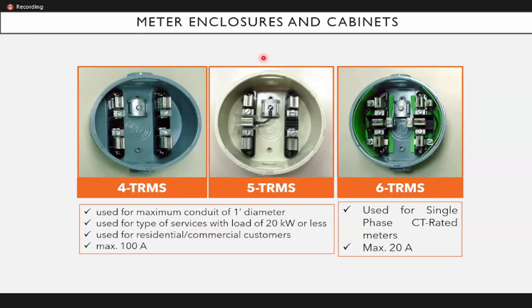So dito po yun. Dyan po nilalagay yung 1 diameter na rigid steel conduit. This is used for type of services with load of 20 kilowatts or less. So normally sa mga bahay po natin ito at sa mga small commercial customers. This socket type has a maximum of 100 amperes. And then for the 6 terminals, this is used for single phase CT-rated meters with a maximum of 20 amperes.